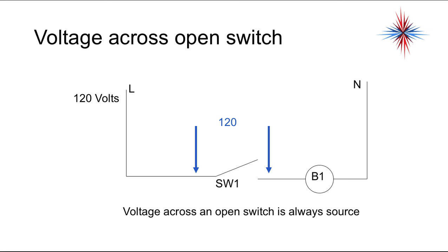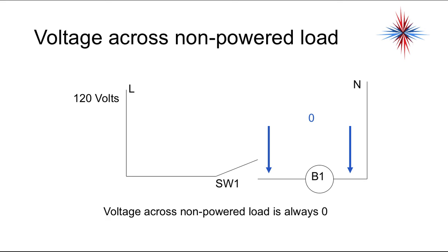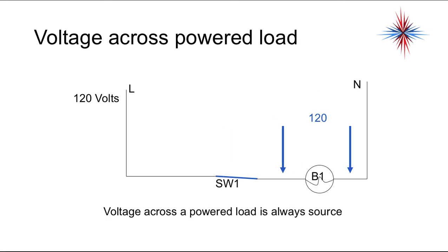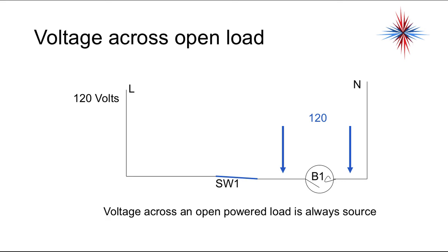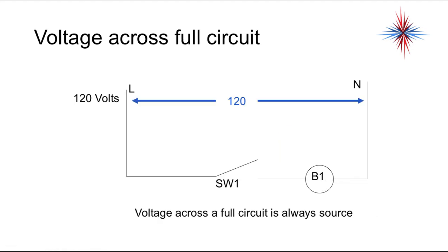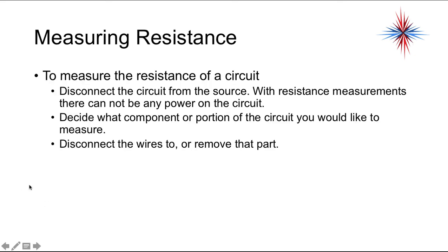So voltage across an open switch is always source. Voltage across a closed switch is always 0. Voltage across a non-powered load is going to be 0. There's no path for electricity to flow to the load. Voltage across a powered load is always source. Voltage across an open powered load, in other words, broken, there's a winding broken or a filament broken, light bulb burnt out, it's always going to be source. Again, because there's an open in that bulb or load. Voltage across a full circuit should always be source. If you don't get source across a full circuit, go find out why.